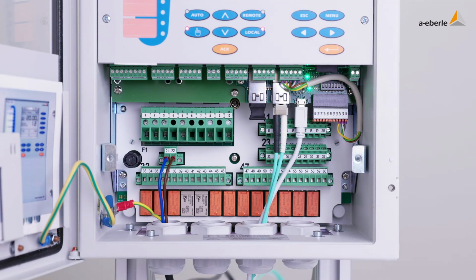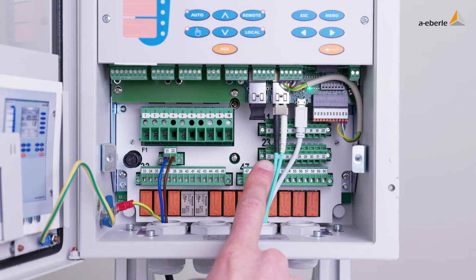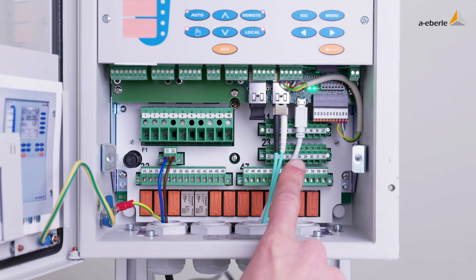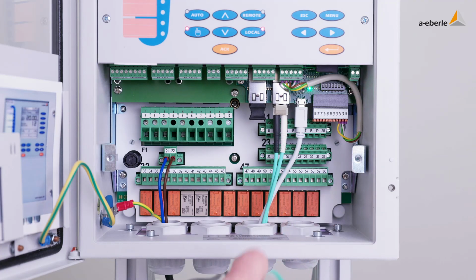Let's get started. For a firmware update, we need two different connections: first the Ethernet connection, then the serial connection. I use the first Ethernet port for the update, but it's also possible to use the second one. Later in the software, you will adjust which port you will use for the firmware update. We also did a video about how to find the first Ethernet port on the SCADA card. During the firmware update, both ports need to be connected.